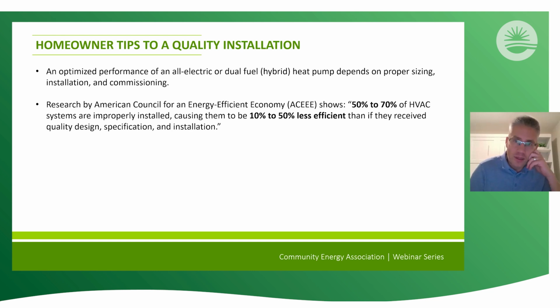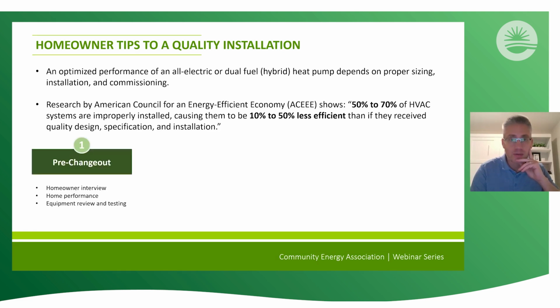And we've got a little data piece here that really reinforces why quality installation is important. Studies have shown that 50 to 70% of systems are improperly installed, and this was not a small sample size, this was a large sample done in North America. The deviation from actual performance is anywhere from 10 to 50%, depending on the issues with regards to design, specification, and installation. So there's a lot of risk in getting the right system. And it's not just about buying the right piece of equipment.